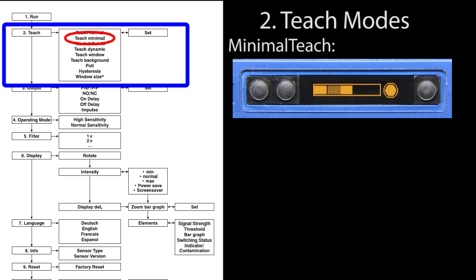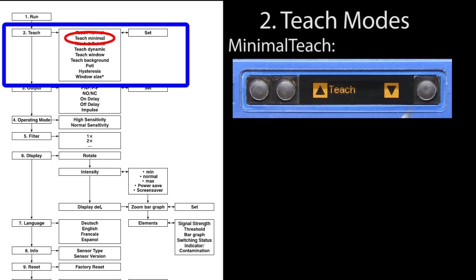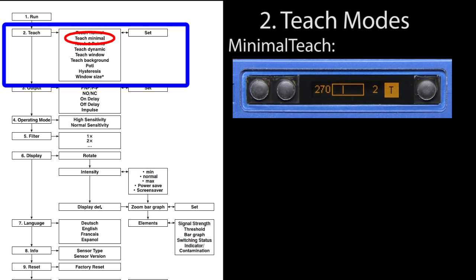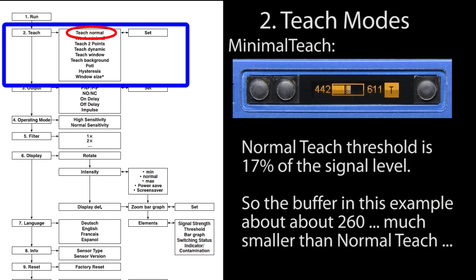Minimal teach is the exact same thing, but let's do it anyway so we can see if we get a different result. Enter into the menu, down to teach, enter into the teach submenu, down arrow to minimal and hit enter. Let's do the exact same thing: set the object near 600 and hit T for teach and it was successful. You can see on the bar graph that the buffer is a lot smaller with minimal teach. Looks like it's around the mid to upper 400s. Remember, minimal teach has a minimal buffer.